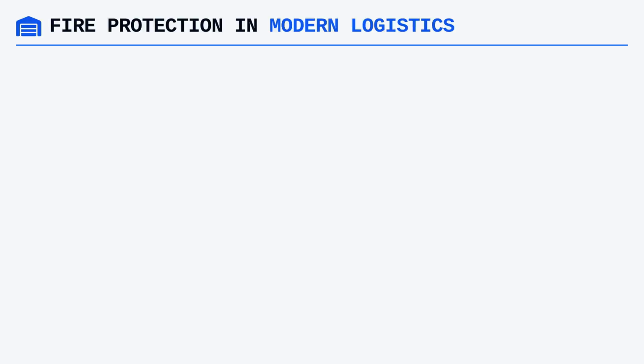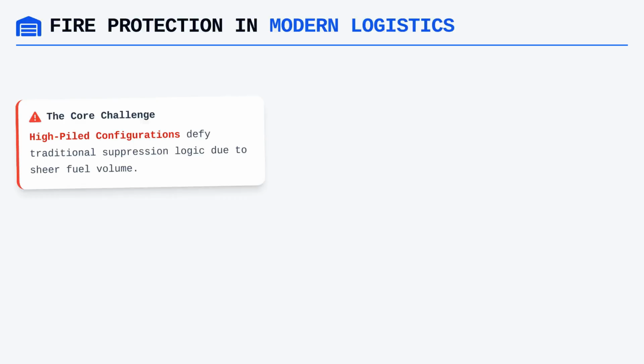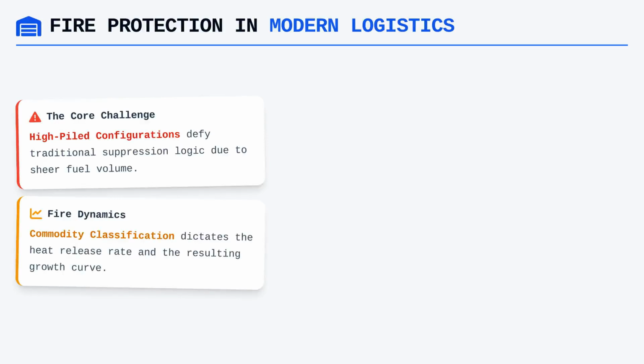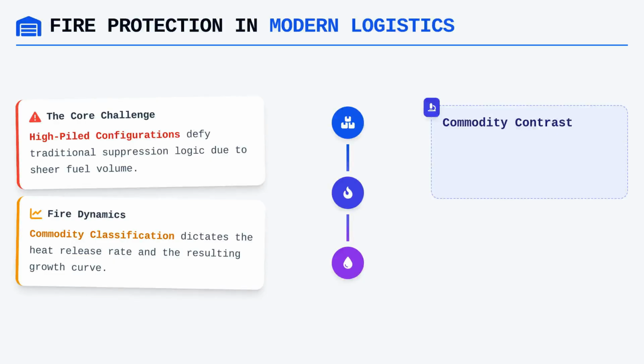Modern logistics centers present a unique challenge because the sheer volume of fuel gathered in high-piled configurations defies traditional suppression logic. When we analyze these environments, our primary concern is the classification of commodities, which dictates the fundamental heat release rate we must design against. We are categorizing products based on their combustibility and arrangement, specifically focusing on how encapsulated plastics or the accumulation of idle pallets radically alter fire growth curves. A plastic product does not burn like a piece of timber. It releases energy at a significantly higher rate, often necessitating a more aggressive suppression response.